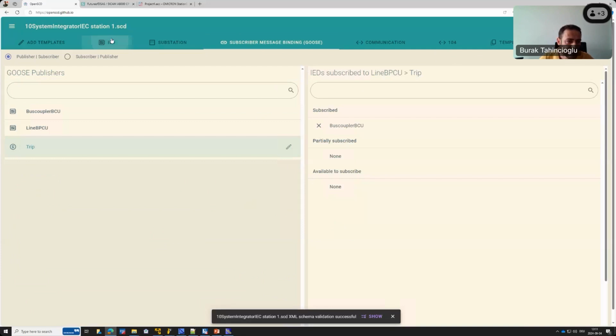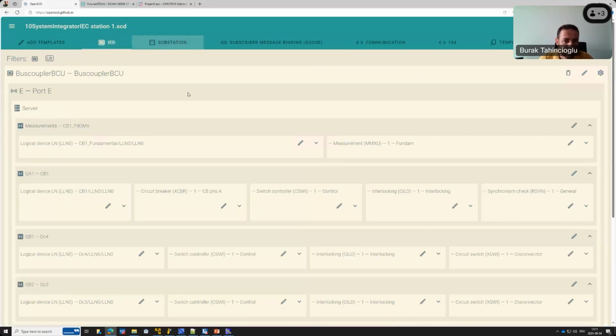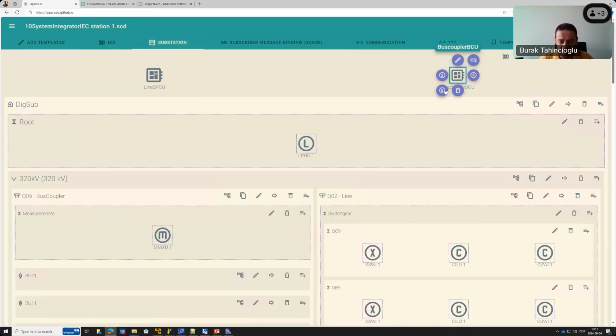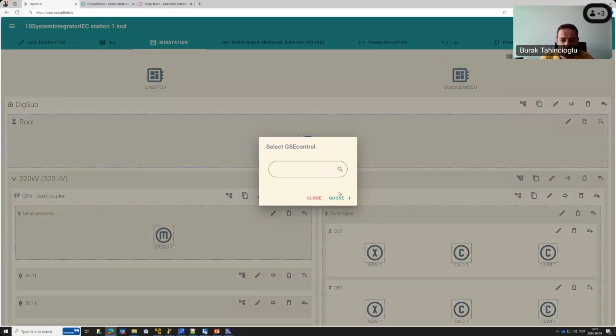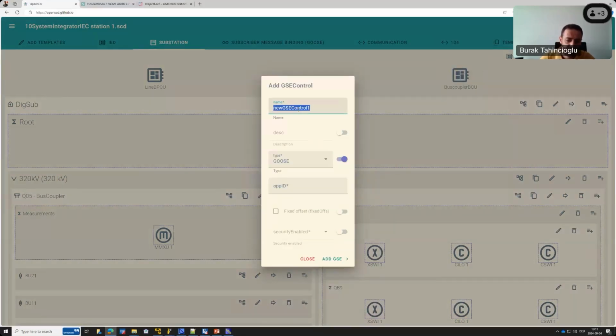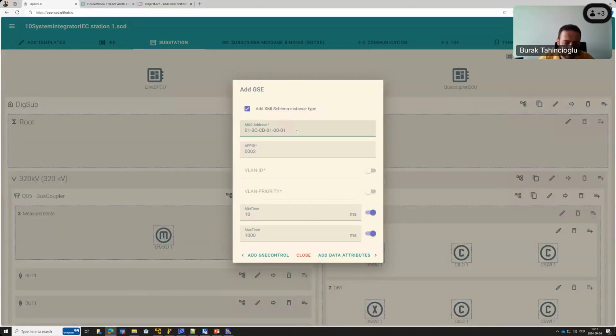I would continue doing the same, creating another GOOSE of the bus coupler, which is sending out information of the switchgear positions, for instance. Then I will use it for interlockings. I will create an application ID, again something descriptive. Then maybe a unique destination MAC address, which allows the switch to understand this better if I want to use some filtering. Also, as I may want to sniff the network, I can use this MAC address to understand what the application is or which kind of information is shared.